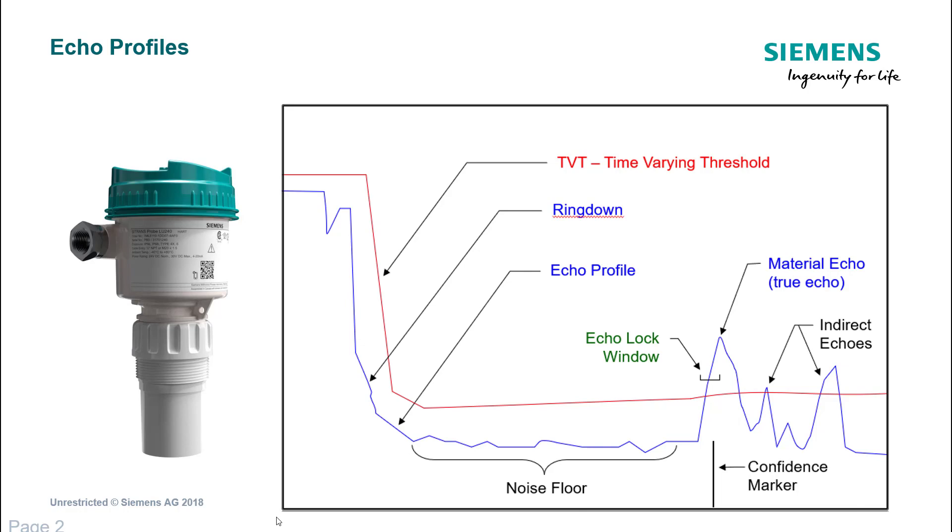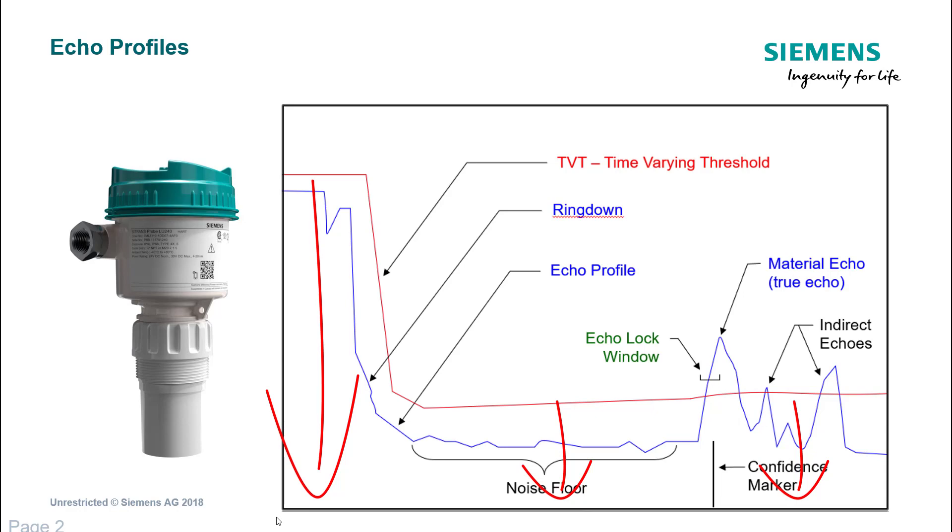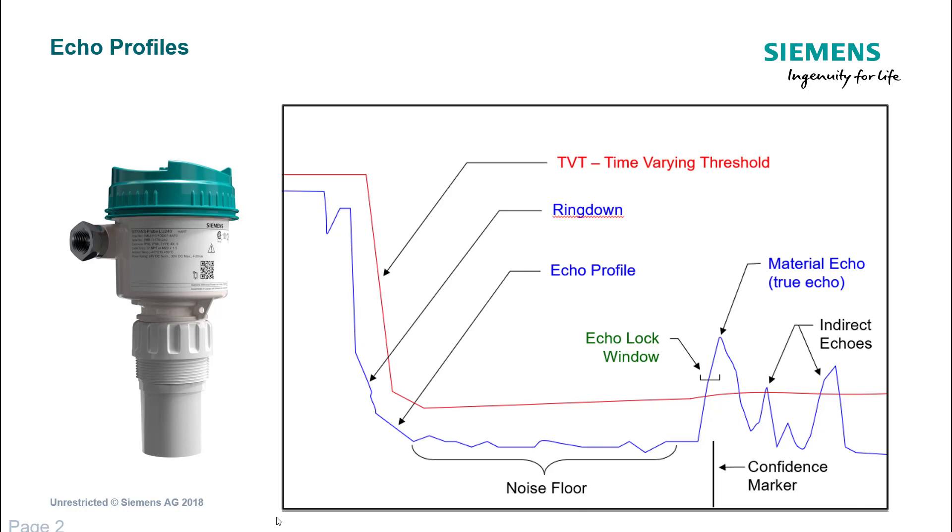The echo lock window ensures that if all of a sudden you get an echo two meters in front of that, it doesn't jump to that echo straight away. You can see this red line. Siemens calls that the time varying threshold. Basically, anything below that red line is not analyzed in the scoring mechanism of how to lock onto the true echo. Think of it as a filter. It filters out the noise floor, and anything blue that protrudes that red line is then scored on different algorithms including the height of the echo and the area of the echo above the red line.